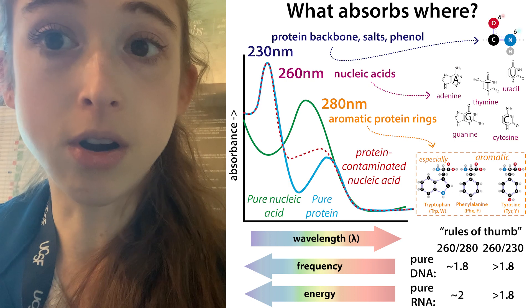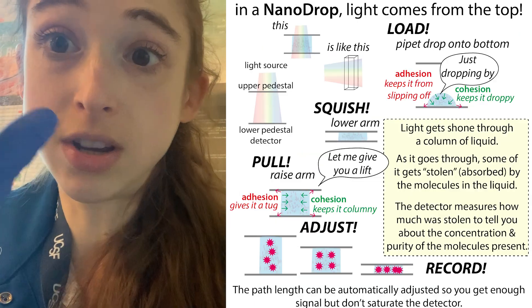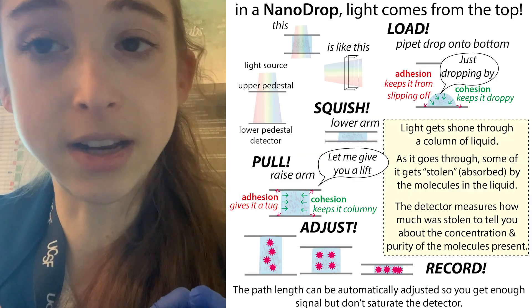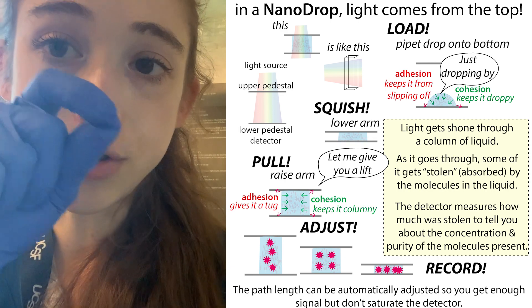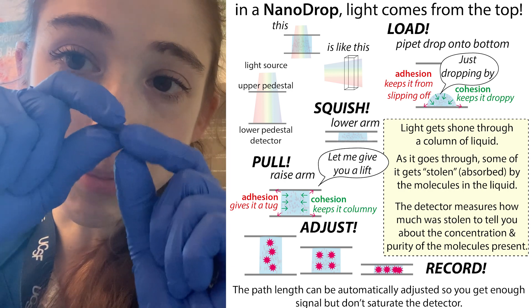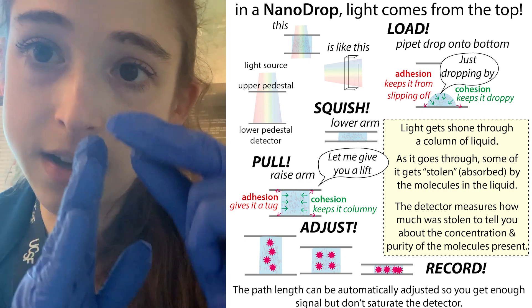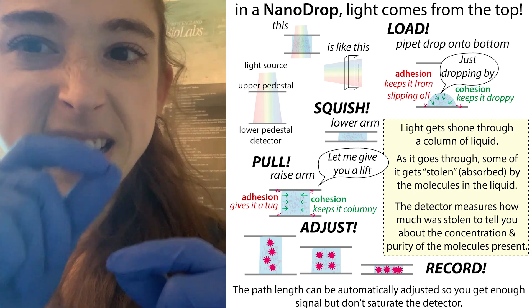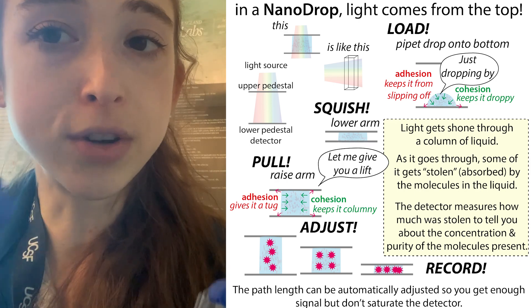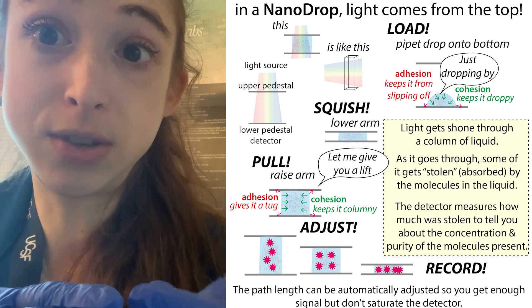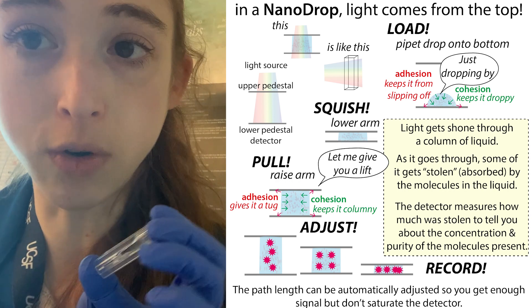There's much more on this in other posts that I'll link to. But today I just wanted to tell you about the coolness that goes on in a nanodrop. You put that drop down, it pulls up to the right length so it doesn't saturate the detector, it figures out the right path length, and then it converts it in its software so that you see the absorbance as if it were taken from a normal cuvette.